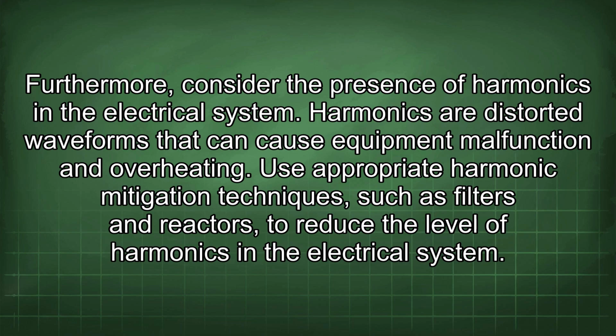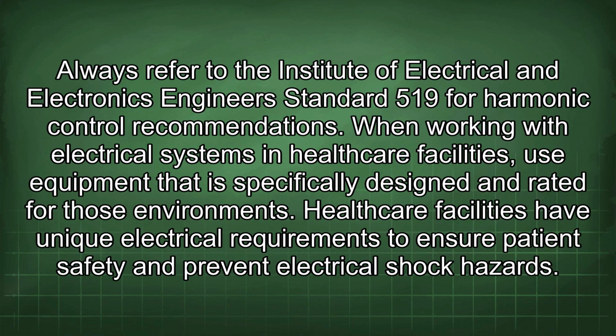Furthermore, consider the presence of harmonics in the electrical system. Harmonics are distorted waveforms that can cause equipment malfunction and overheating. Use appropriate harmonic mitigation techniques, such as filters and reactors, to reduce the level of harmonics in the electrical system. Always refer to the Institute of Electrical and Electronics Engineers Standard 519 for harmonic control recommendations.